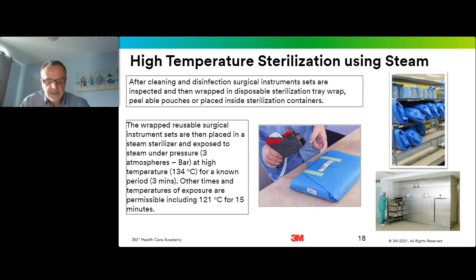So let's now take a look at high temperature sterilization. Now, this, of course, is the next big step where water will be used in our reprocessing cycle. Because, as I mentioned earlier, maybe 85-90% of reusable medical devices are re-sterilized in steam sterilization processes. And in this process, steam at high temperature, typically 132-134 degrees C, and pressure up at 3 bar are used to sterilize the instrument surfaces.